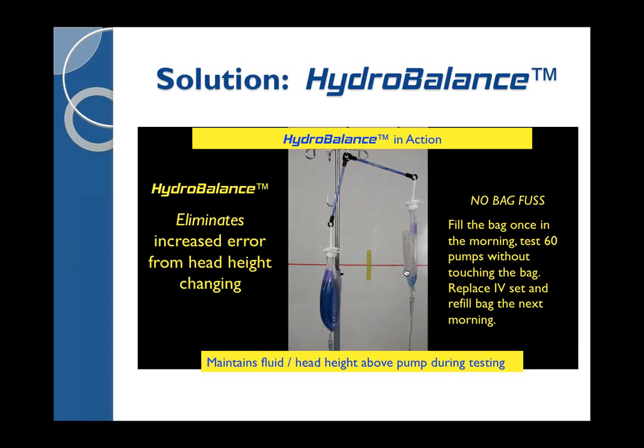So by doing this, you can eliminate the error of up to 1% on the IV pump performance from the time that your IV bag is full to the time that your IV bag is empty. For those of you that do a lot of IV pump testing, this could be a big deal. Not only can you increase the accuracy of your test setup, but you can reduce the amount of fuss factor with refilling the IV bag. Essentially, if you fill the IV bag up to 1,200 milliliters, you can do that once every morning, put a new IV set on, and not have to touch the IV bag or IV set again until the next morning. So you can gain accuracy as well as gain efficiency in your infusion pump testing, which can be a huge deal if you've got 1,000 IV pumps to test in a month.